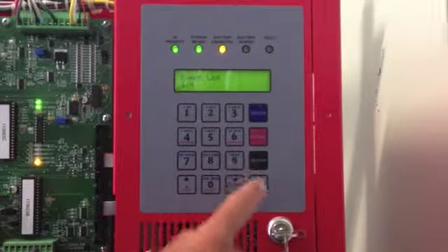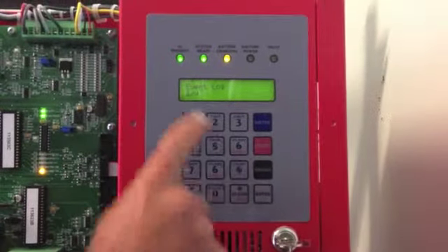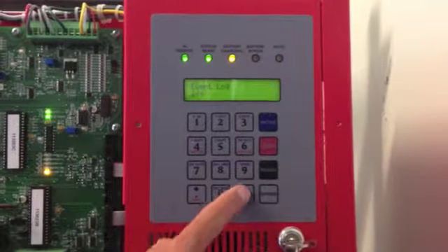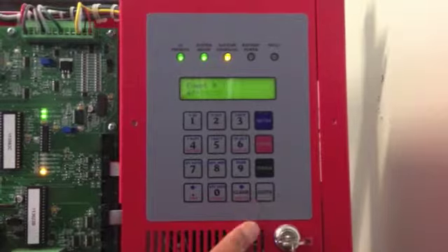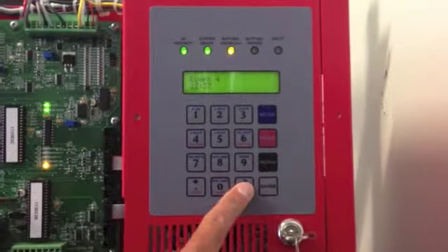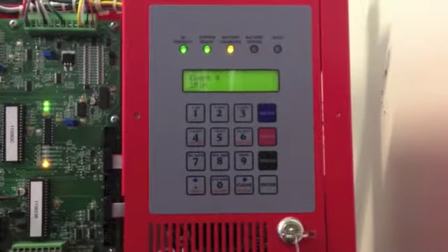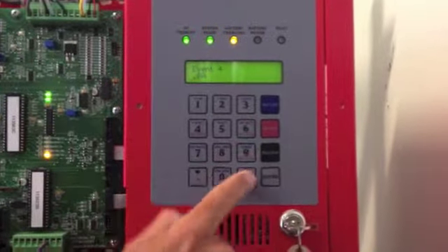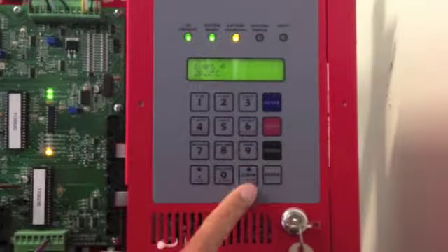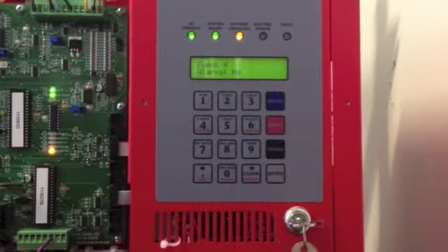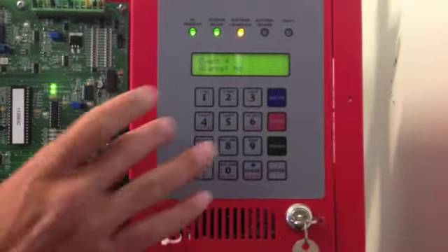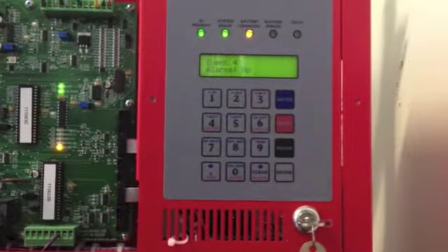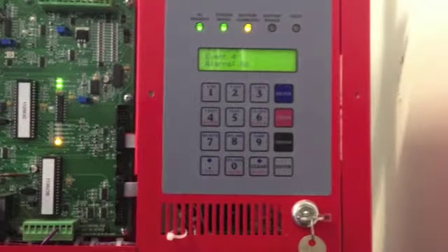When we look at it, this is the event log, but we'll see the same information basically. It'll say test log and one of however many tests there are. We scroll through and we select any one. We'll get the date, the time, and the duration, which again are all predetermined. And then we'll see that we had good output voltage, we carried our load, temperature was acceptable, and we had no alarms. The key when checking our test log is that we ran the full duration, 5 or 90 minutes, and there are no alarms. That's really what we want to see there.